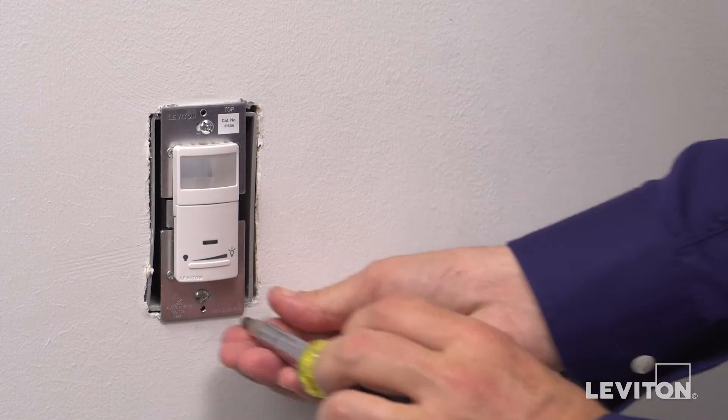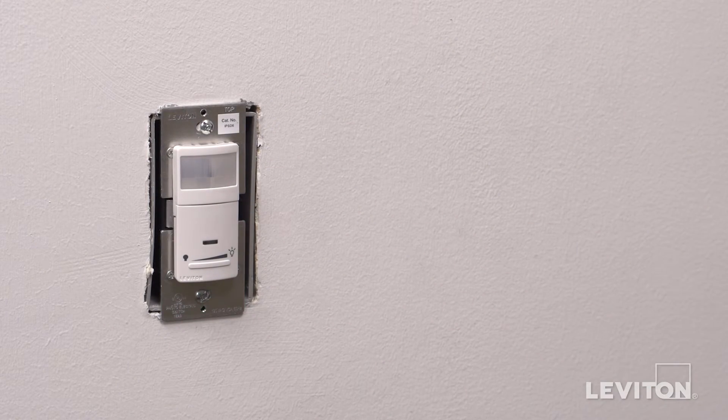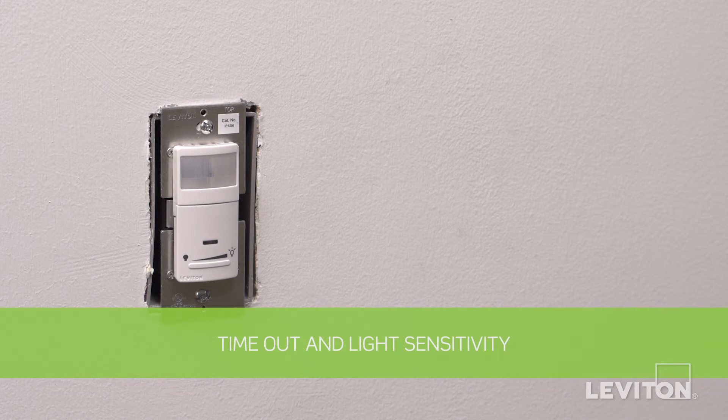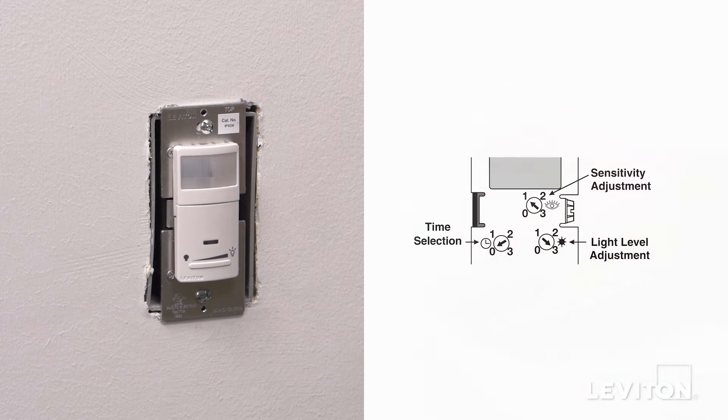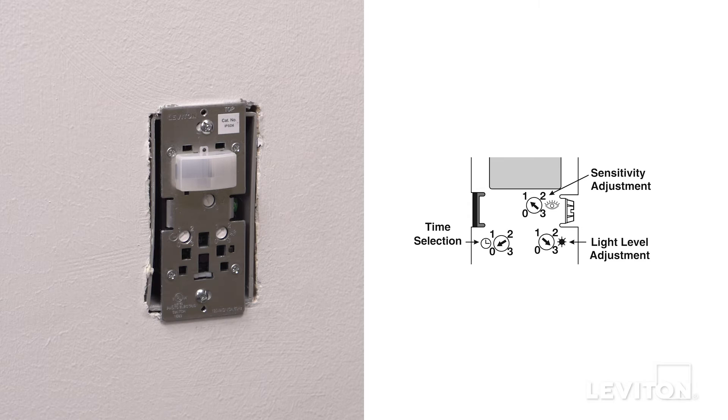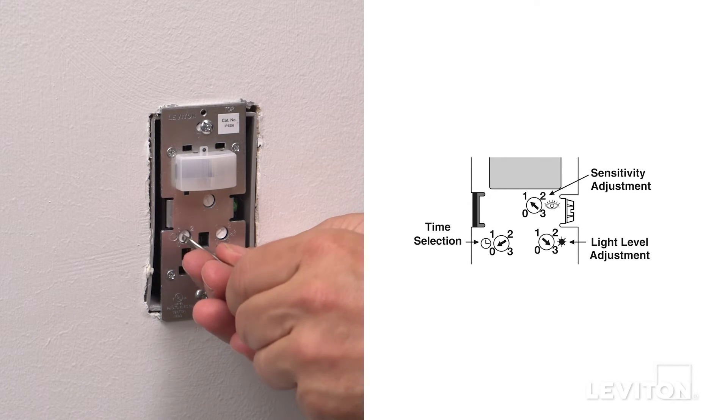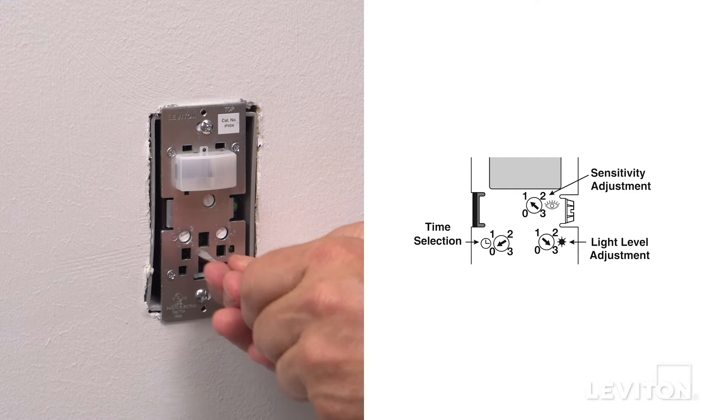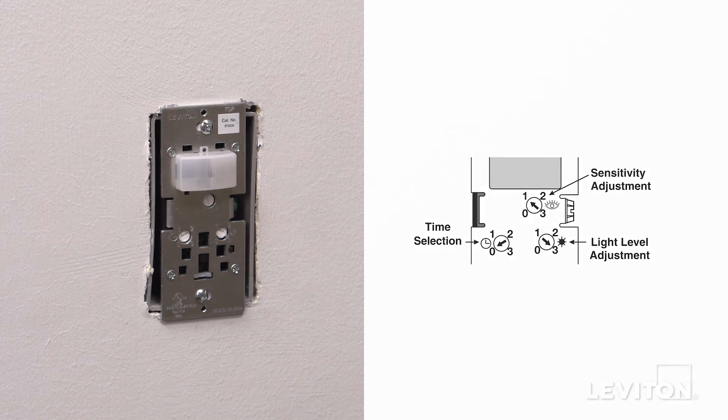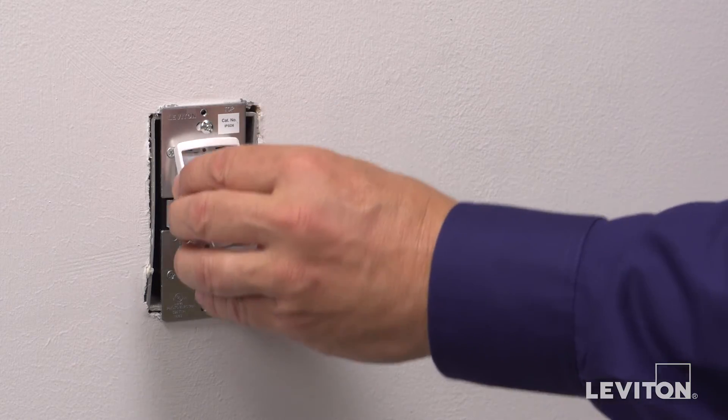We will now test the device prior to mounting in the wall box. First, we will adjust timeout and light sensitivity levels. Remove the face cover of the sensor to expose the adjustment dials. Set time selection of the sensor to 30 seconds for a quick timeout during testing. Set the light level dial full clockwise. Place the face cover back on the sensor.